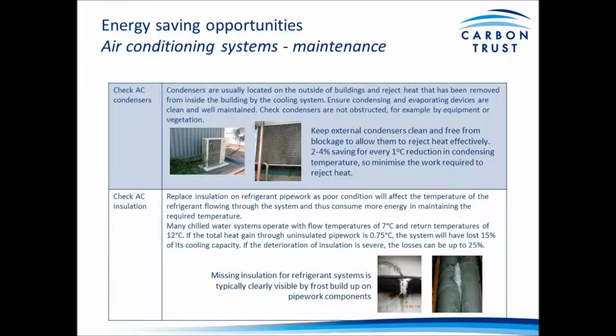Insulation, as with heating, is key, and it's often very visible in cooling systems. If you have cracked pipework, often due to the cold temperature of refrigerant, you can get frost buildup. And there's this example here. Notes: many chilled water systems operate with flow temperatures of 7 degrees C and return temperatures of 12 degrees C. So if the total heat gain through uninsulated pipework is 0.75 degrees C, the system will have lost 15% of its cooling capacity. And that's purely down to poor insulation, not any load on the system.